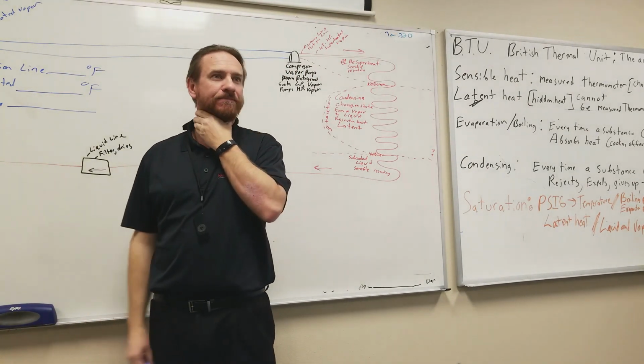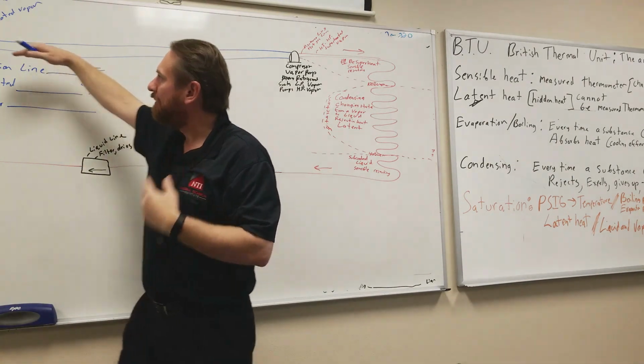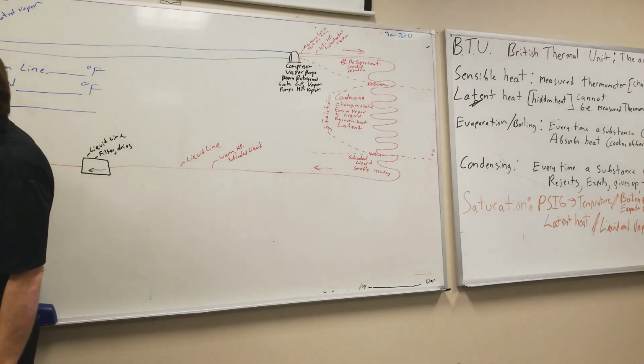Make sense? So it's an important thing. That's why we always want to have this number on top. Is my suction line temperature warmer than saturation?